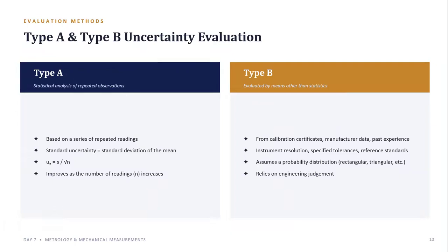Let us now discuss type A and type B uncertainty. The measurement uncertainty can be evaluated using two principal approaches, type A and type B evaluation. Type A uncertainty is evaluated using statistical analysis of repeated observations. For example, when repeated measurements are available, the standard uncertainty can be estimated from the standard deviation of the mean. The presentation gives the following relationship. UA is equal to S divided by root of N, where S represents the standard deviation and N represents the number of observations. As the number of repeated observations increases, the statistical estimate generally improves.